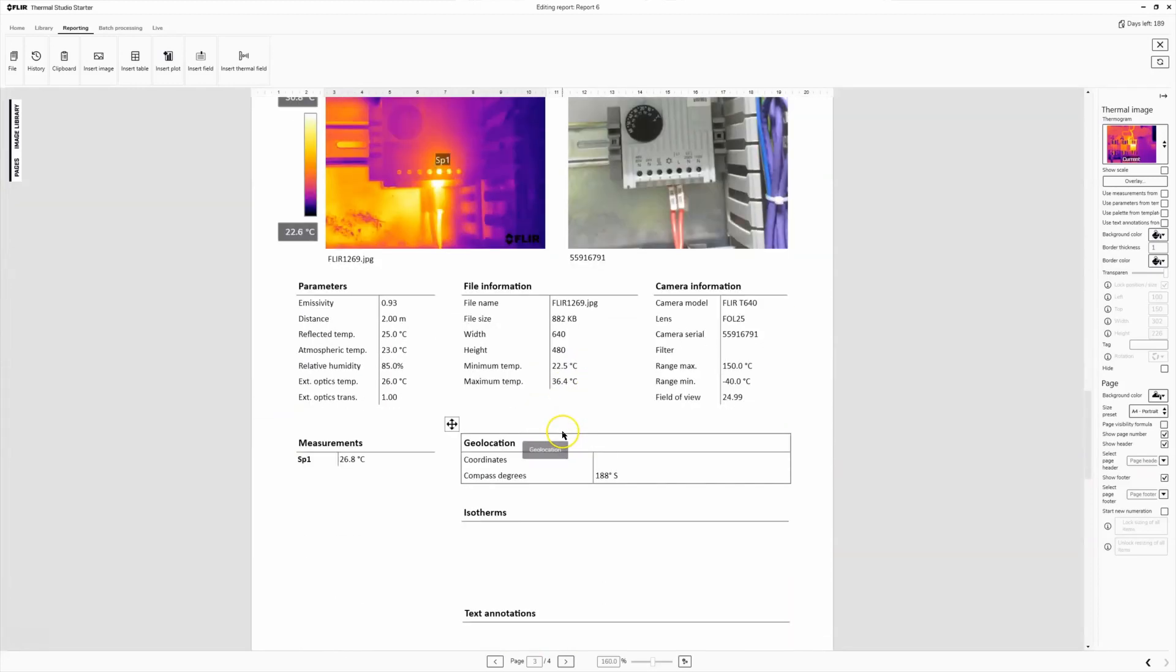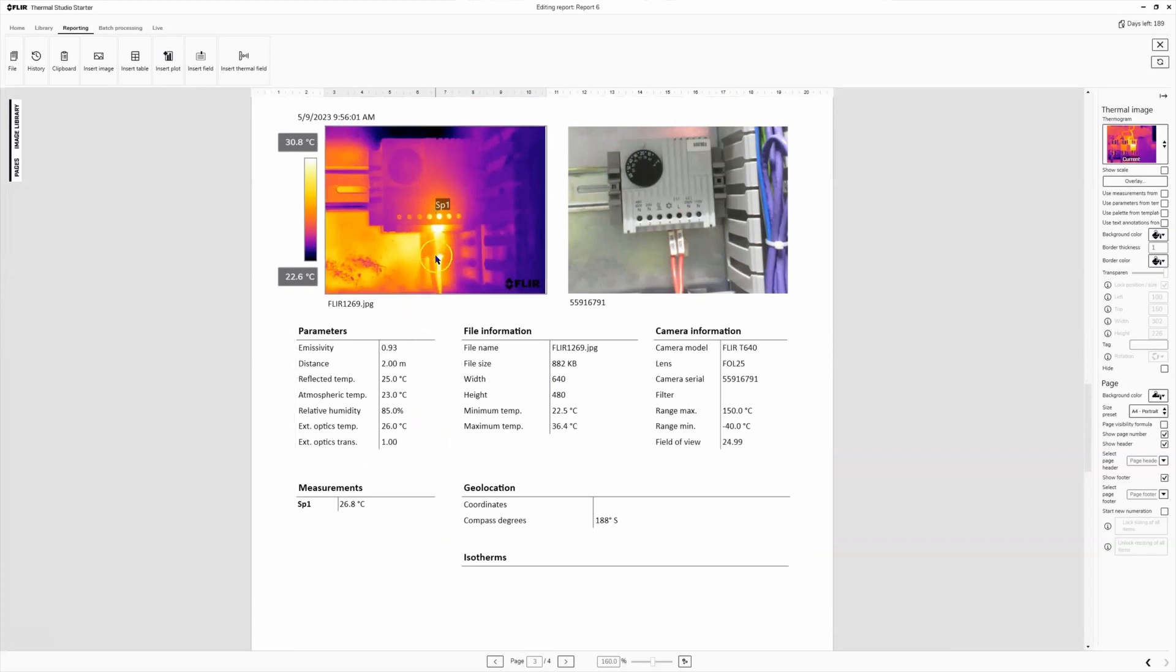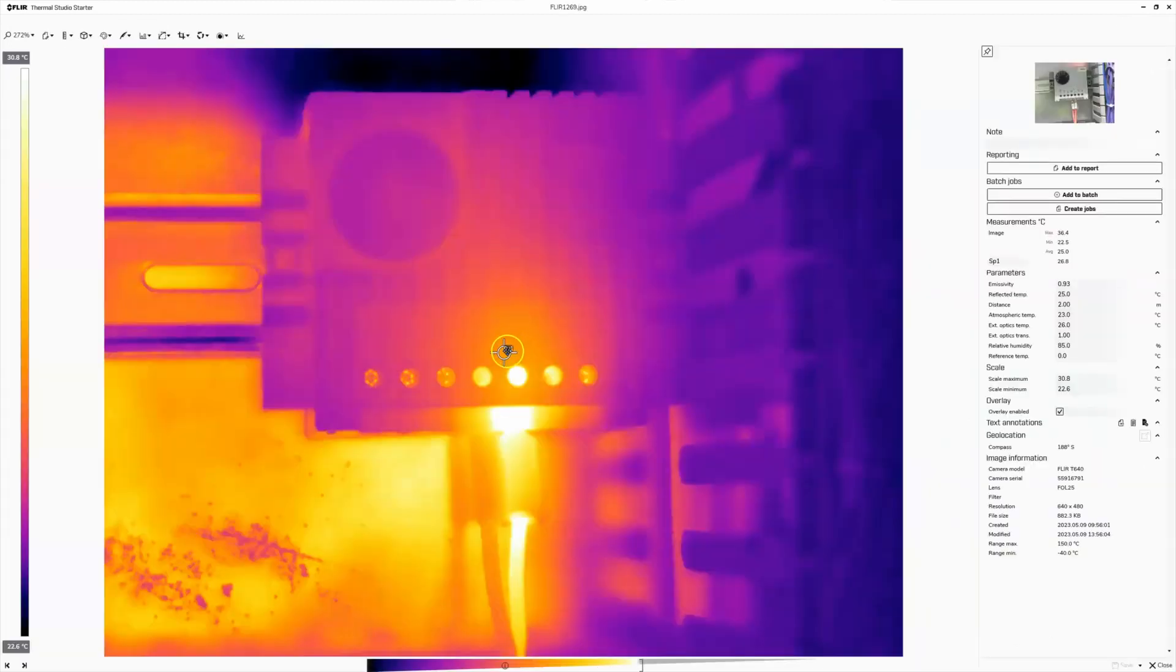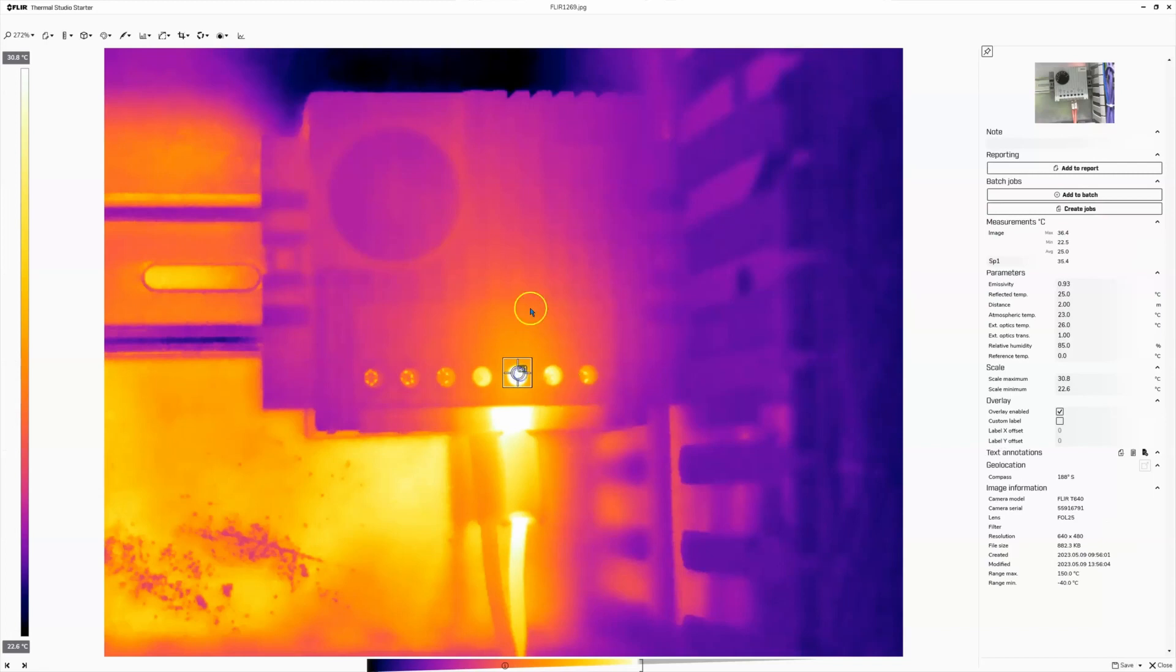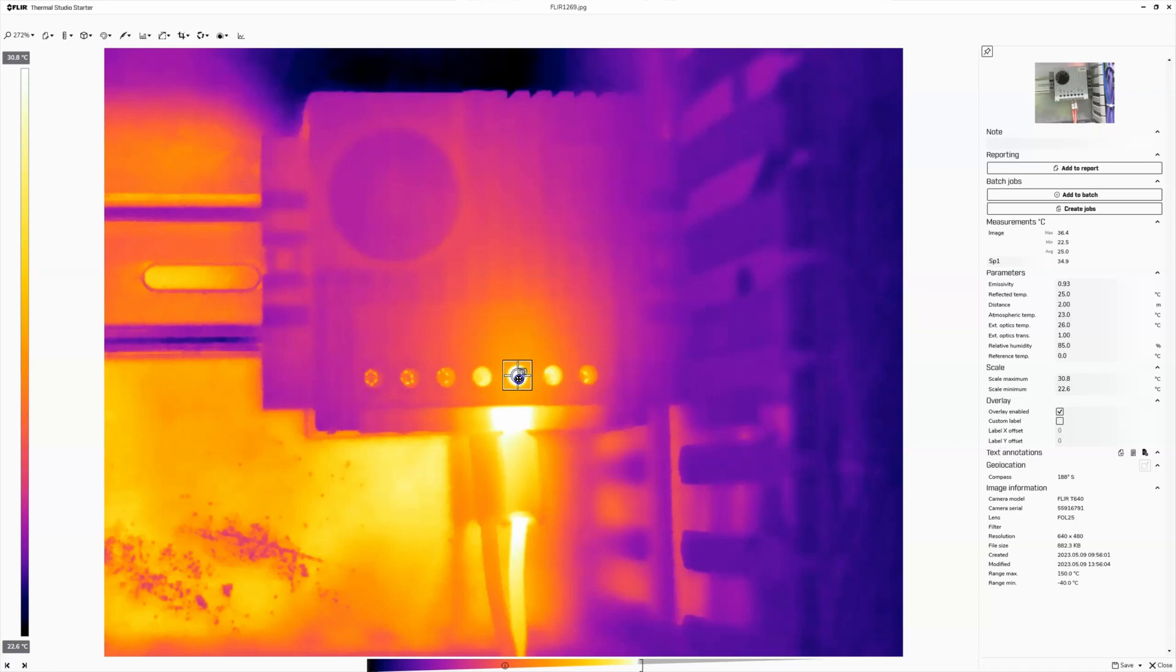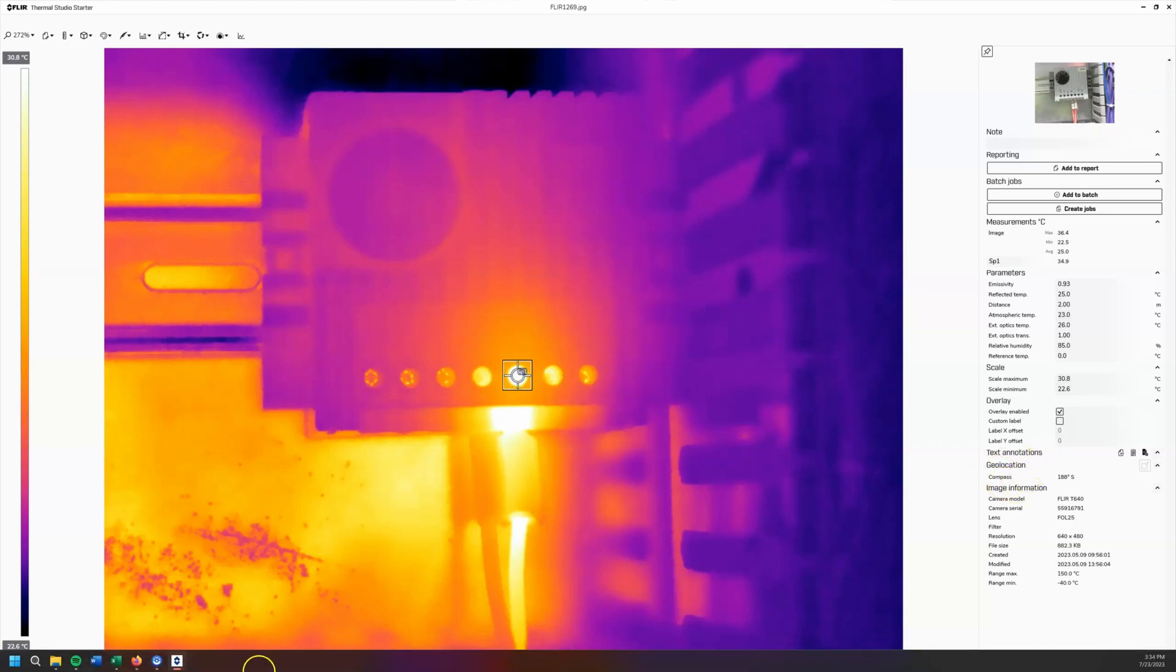We'll do the same thing here. So I'm just going to double click on this image. I can just click and drag the existing spot to wherever the hottest spot is. This is really funny because it's a thermostat. So it controls a small heater. And the wire was actually warmer than the heater was. So that's an interesting thing to snap a picture of.